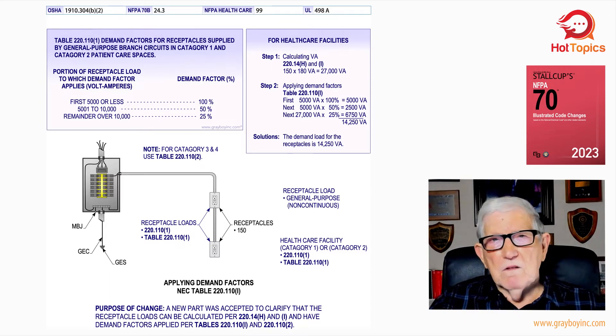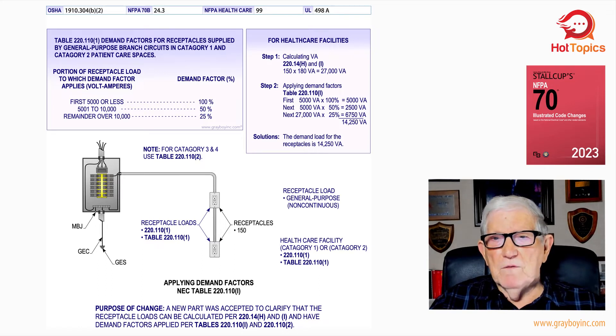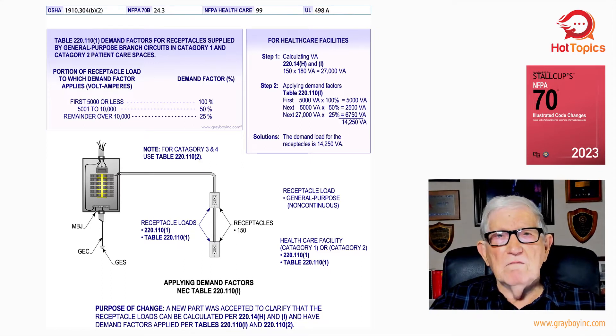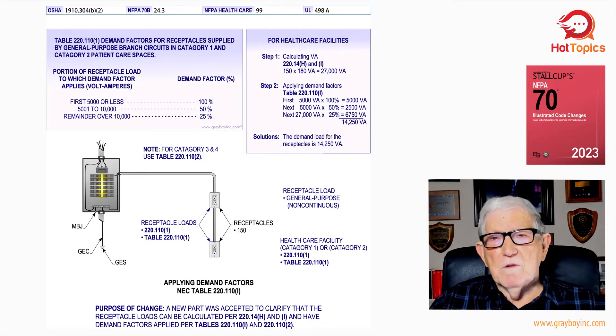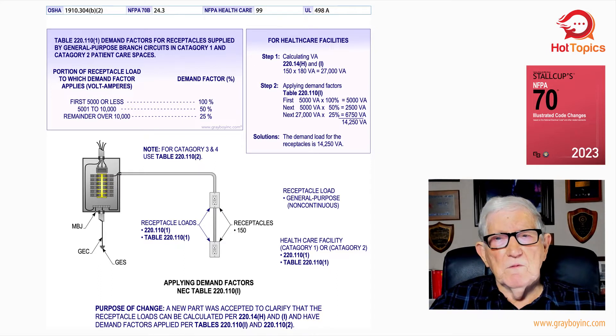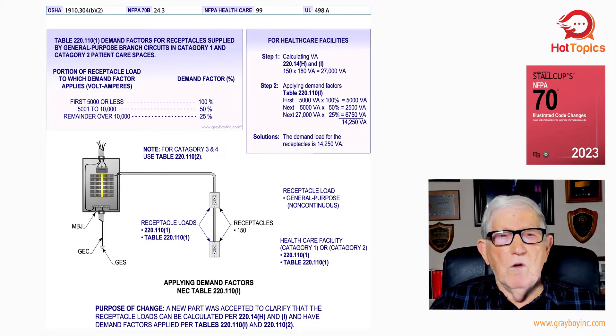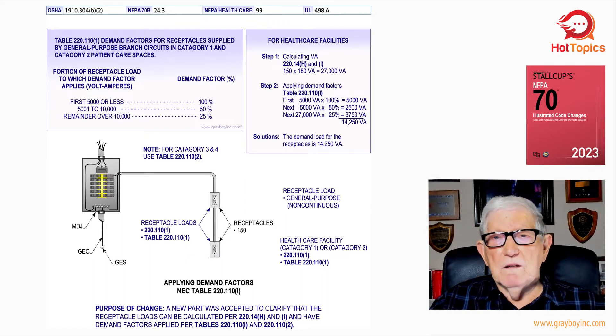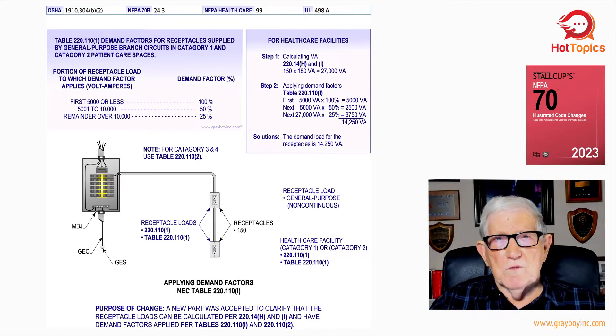That's quite a demand reduction — where in step one it was 27,000, we applied demand down to 14,250. Basically, what they're saying is: if you only had 5,000 VA, then 100% of that — they're saying all of that might be used. But anything over 5,000, they'd take it at 50%, saying maybe 50% of those would be used. And then anything over 10,000 — in this case 27,000 — at 25%, they're saying only 25% of those receptacles would probably be used.